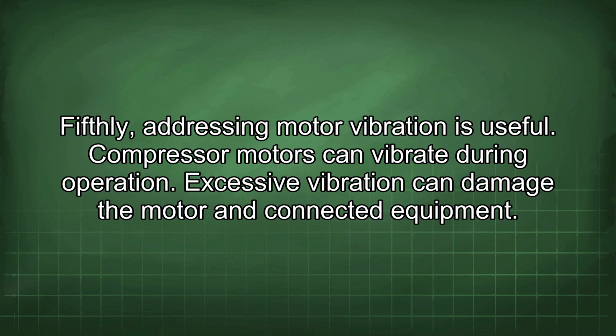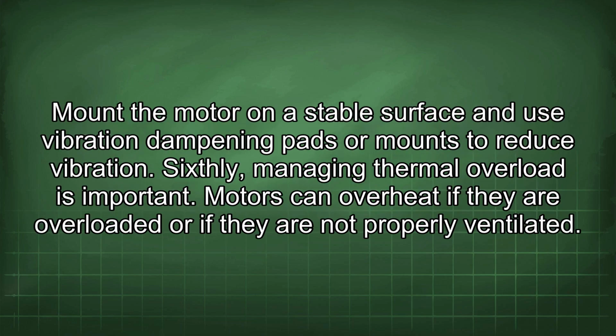Fifthly, addressing motor vibration is useful. Compressor motors can vibrate during operation. Excessive vibration can damage the motor and connected equipment. Mount the motor on a stable surface and use vibration dampening pads or mounts to reduce vibration.